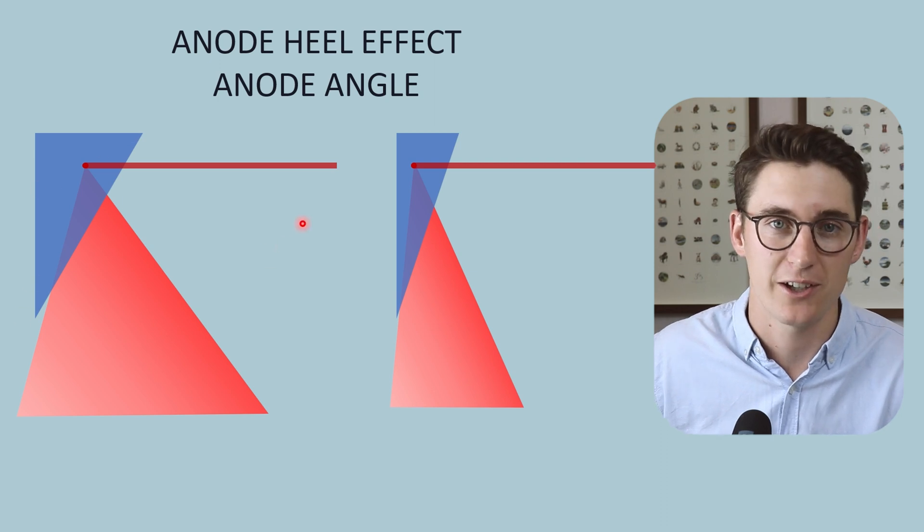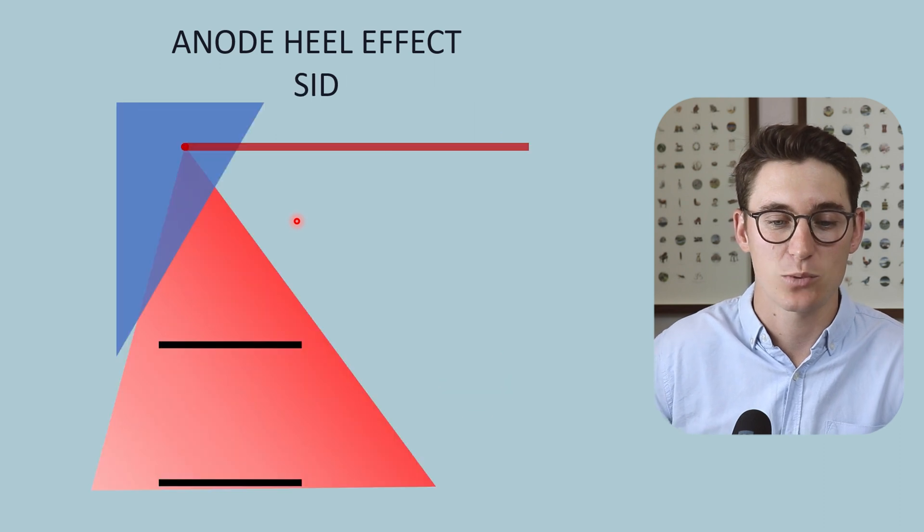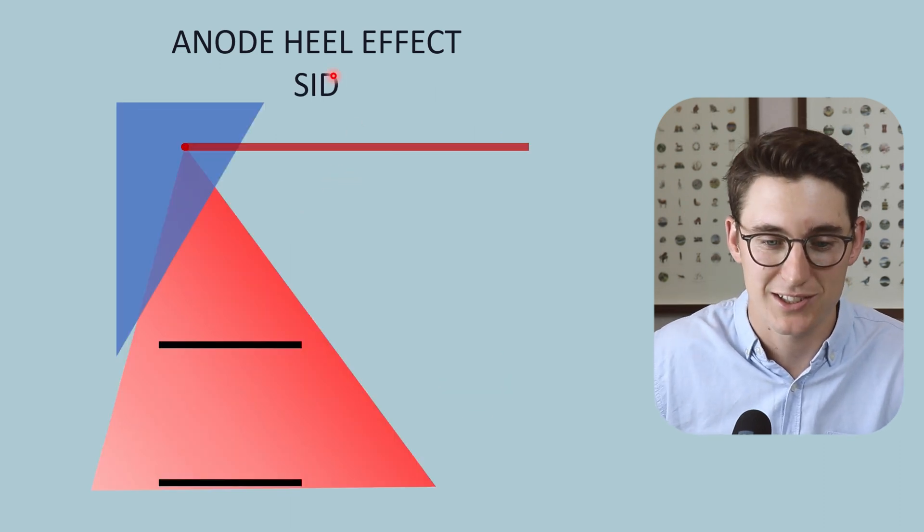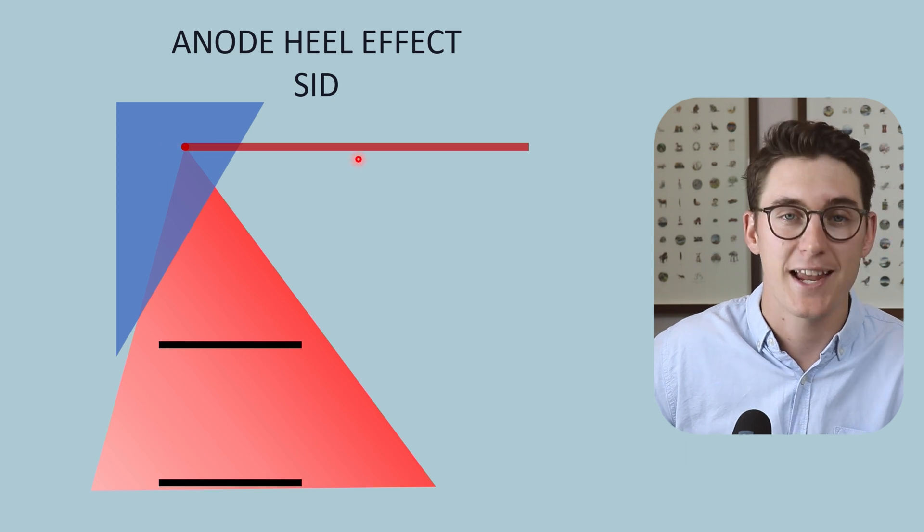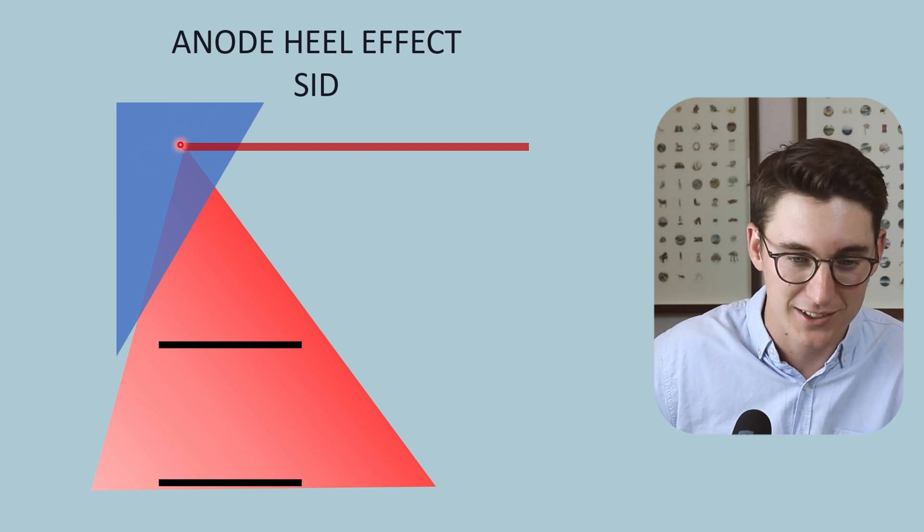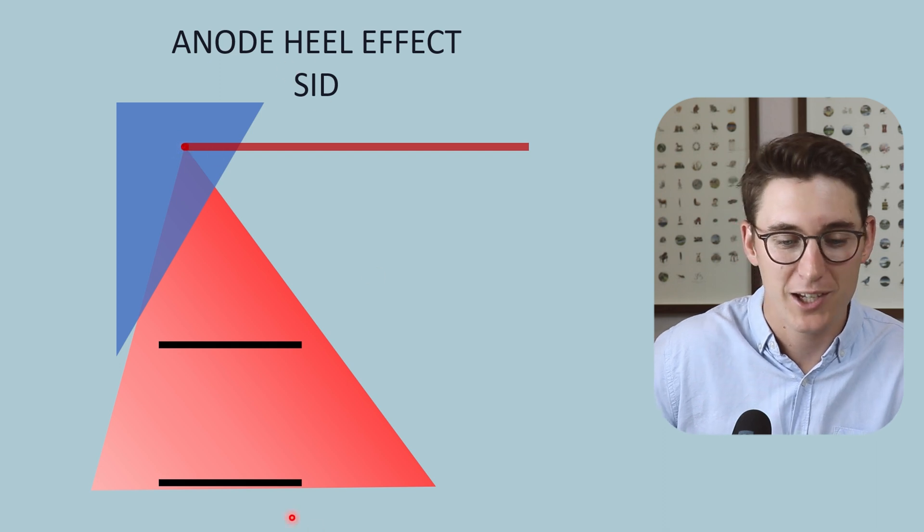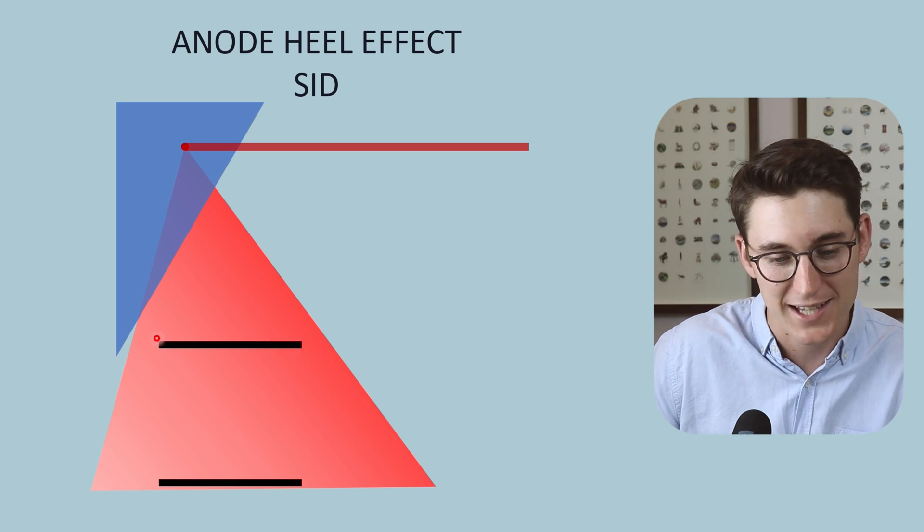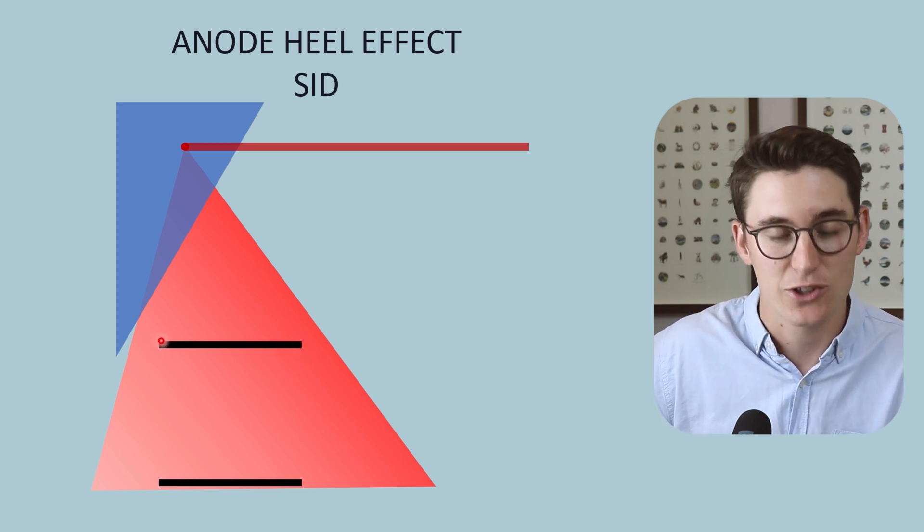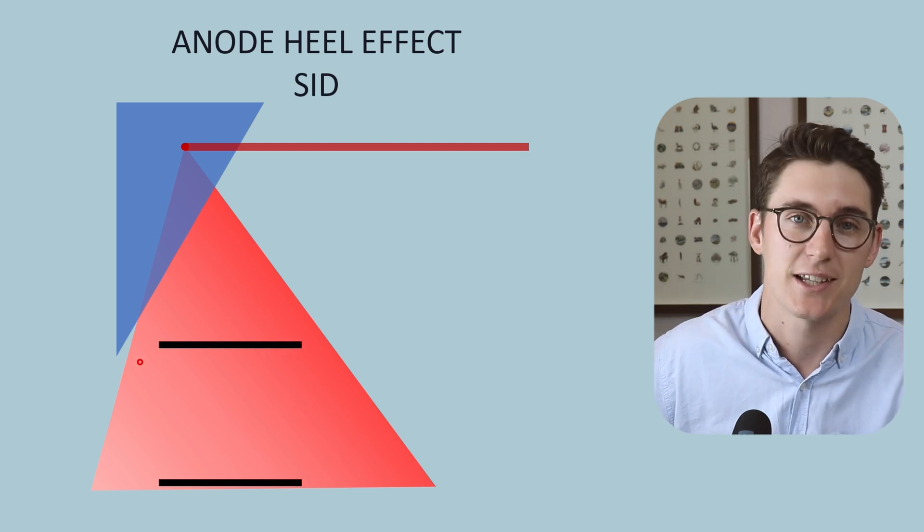The second thing that changes our anode heel effect is what's known as our source to image distance. Our source is where x-rays are produced, where electrons interact with our tungsten in our anode and produce x-rays. That is our source. Our image refers to where the image is created, our detector or our cassette that is detecting x-rays. They've passed through the patient and now they're hitting our x-ray detector.